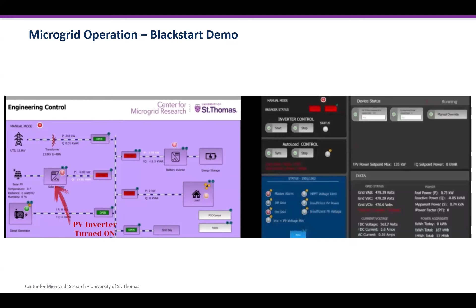Now we are starting the inverter control, switching on the inverter, turning on the PV inverter. As you can see, the power of the energy storage turned negative because the PV is supplying power to the ESS, to the batteries.